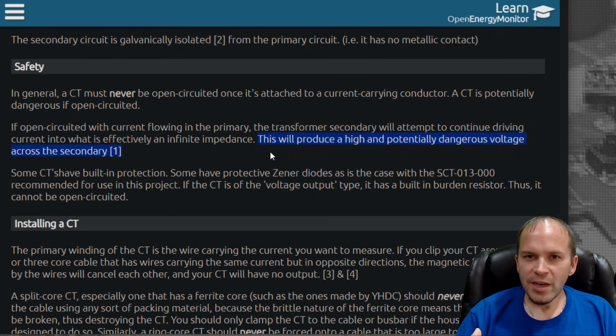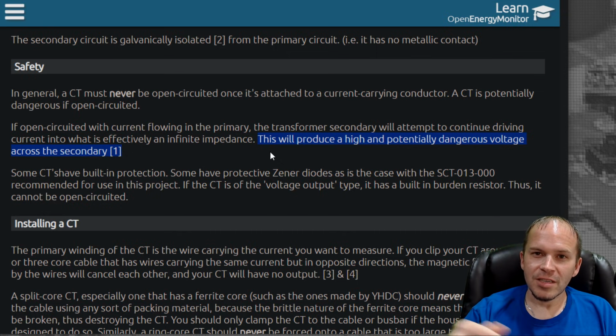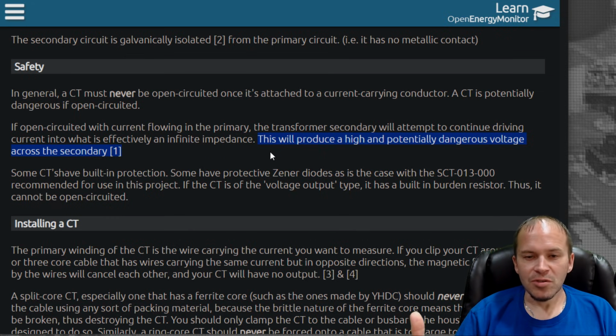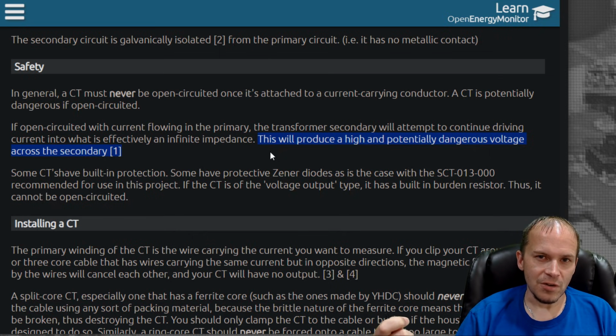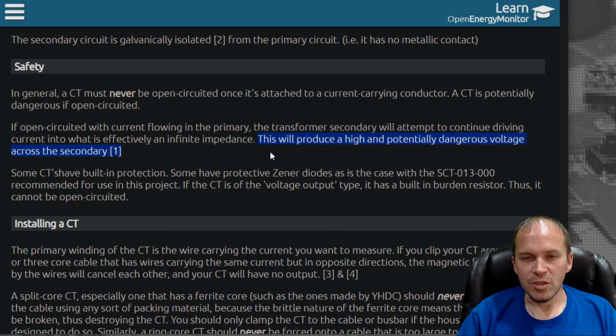If you don't read any of it, definitely read the sentence we highlighted here: if you unplug it, this will produce a highly dangerous voltage across the secondary, meaning that tip could become hot even though you've simply unplugged it from the power monitoring board, while all the power going through your home is still passing through that CT clamp. All in all it's pretty safe, but you need to know what you're dealing with when doing whole home energy monitoring.